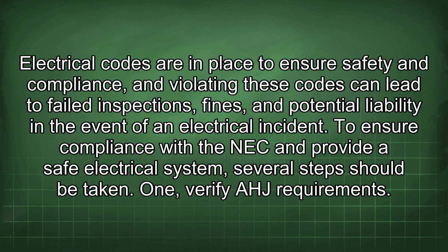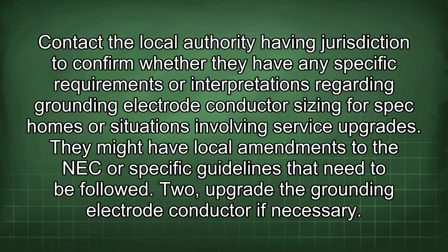1. Verify AHJ requirements. Contact the local authority having jurisdiction to confirm whether they have any specific requirements or interpretations regarding grounding electrode conductor sizing for spec homes or situations involving service upgrades. They might have local amendments to the NEC or specific guidelines that need to be followed.